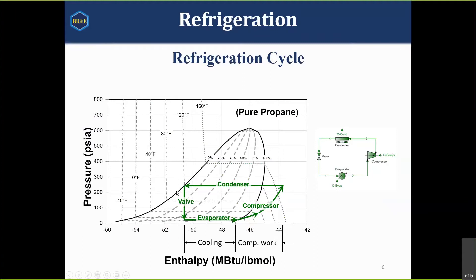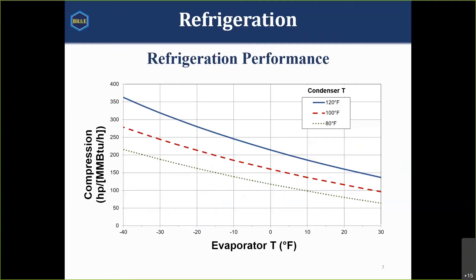Decreasing refrigerant in circulation reduces total power requirement — we're not pushing against a higher pressure in the compressor, and the moles going through the compressor go down, so you have a double effect from lower condenser pressure. Looking at compressor power as a function of condenser temperature, as the condenser temperature goes from 80 degrees up to 120 degrees, power requirements go up.